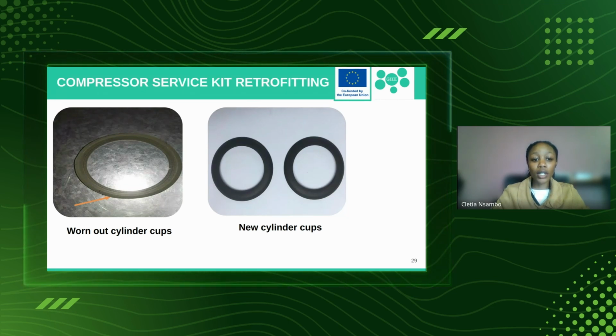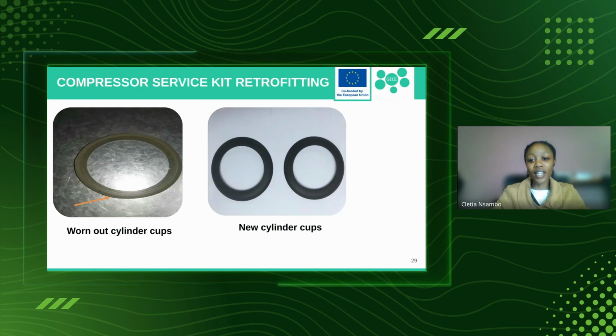So once a cylinder cup is worn in a compressor, when you're servicing, you need to put in a new one. This is where the dimensions come in, because as long as they have the same diameter, you can use the cylinder cup on another compressor. So all you need to know is which ones share the same diameter or different dimensions so you can fix them. You can measure depending on the ones you have at your facility.